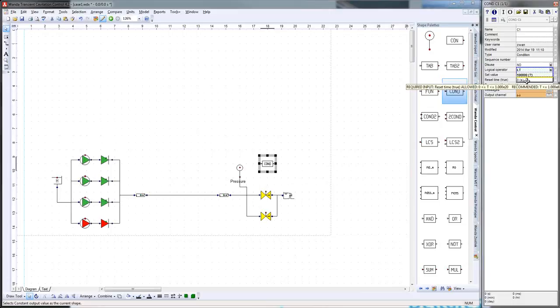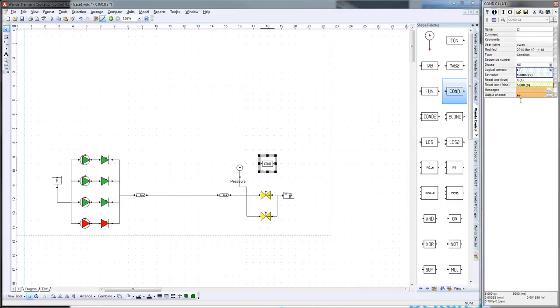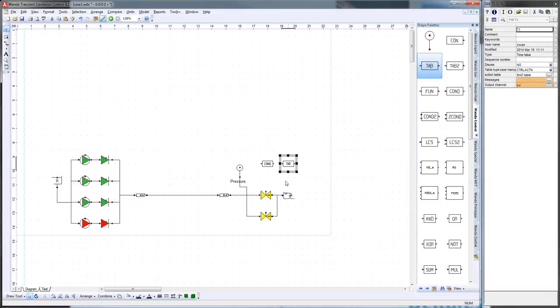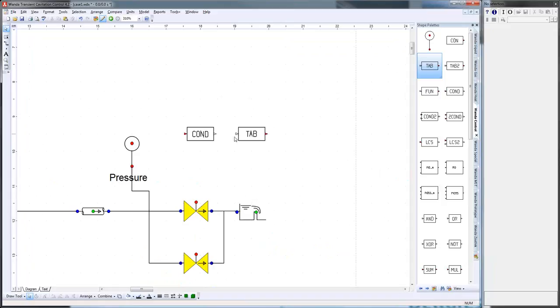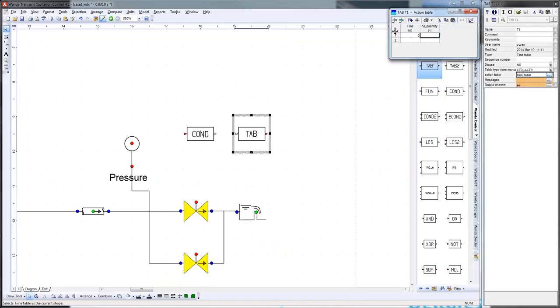Then you have here the reset time. If I put here a time for one second, for example, then the pressure needs to be one second below one bar before it starts operating. But I don't want that - I want immediately the action. However, the signal becomes false again as soon as the pressure becomes above this value, so I don't want that. I want to wait five seconds before it can become true again - that's reset time false - I'm going to put it to five seconds. At the moment the signal becomes true, I need an action, so I'm going to put in a table. If this input becomes true, then the table is going to be used. I put it at 1, and I close the valve in five seconds to zero.